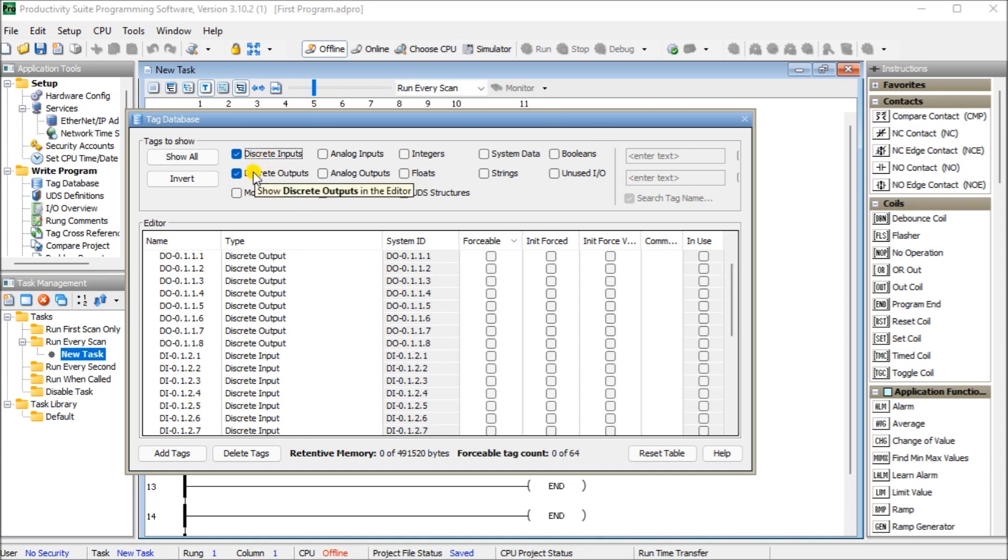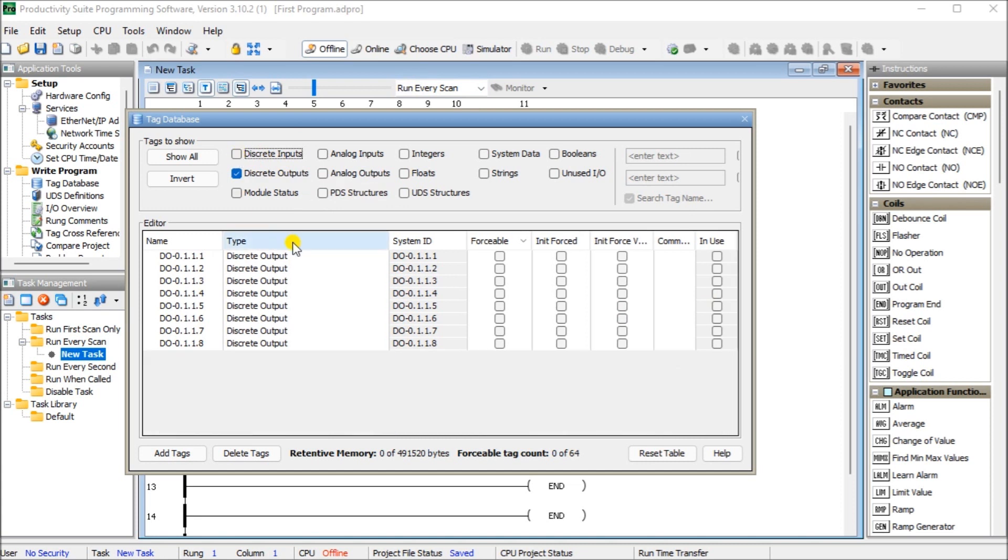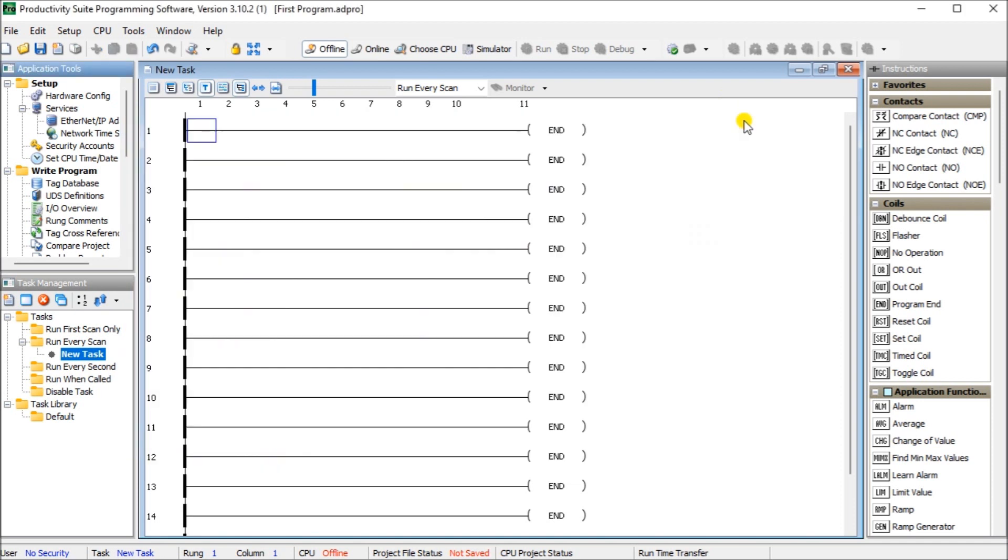And what you'll notice is on our output, we have other options here, less forcible. Now, forcible means that during the operation of the controller, we can actually turn on and off this bit and it will either stay on or stay off or forced either direction or either way. Independent of what the PLC program or the scan is doing to that controller. So it'll keep that point on a rock. So let's just turn on that one first forcible here. So now we have our first output here and that's one we're going to be programming itself. So again, we'll just close that down. So that is our tag database. And we'll discuss more of that later.